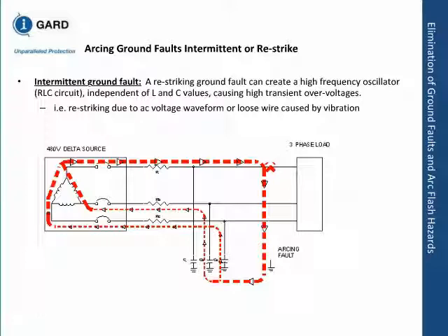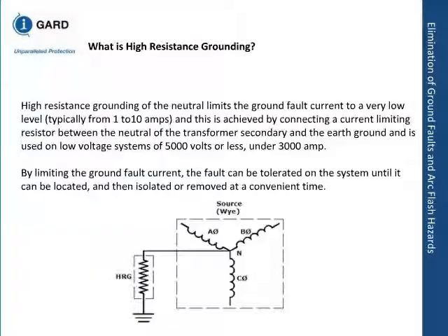So what is a high-resistance grounding system? All of you know basically Ohm's law: current is equal to voltage divided by impedance or resistance in the circuit. So if we want to cut down the fault current level, all we have to do is insert some impedance in there. That is the basis for high-resistance grounding. We will bring it down to 5 amps, or less than 10 amps. So during the first fault, you do not have any arc flash. At 10 amps, an arc cannot sustain itself and it will go away.